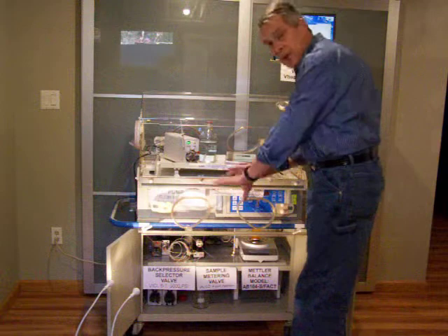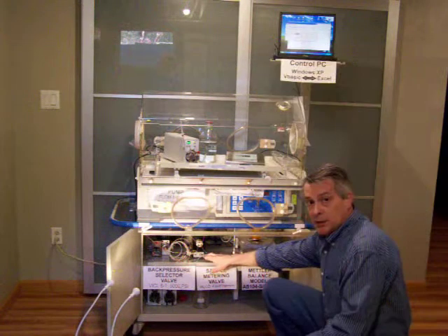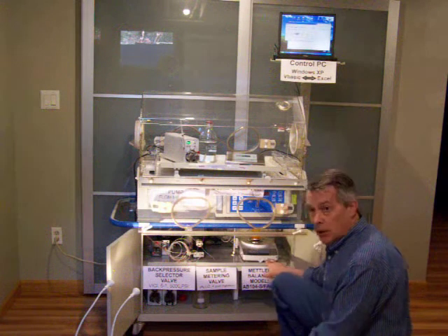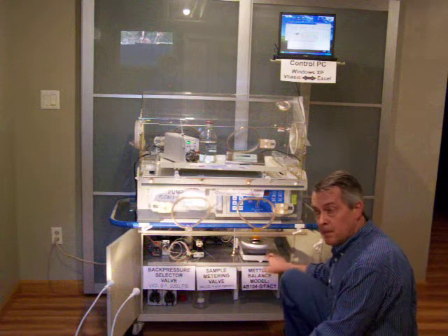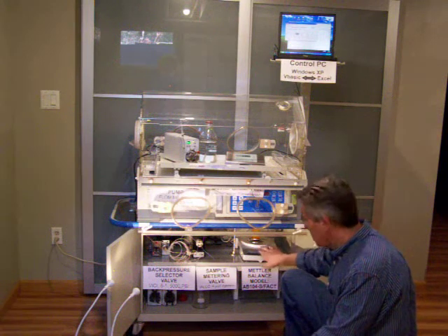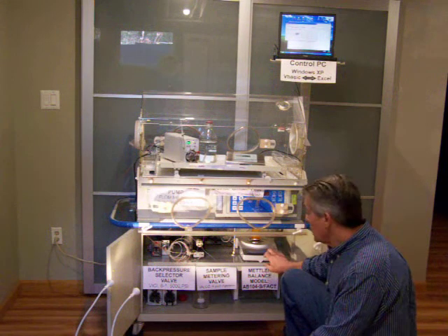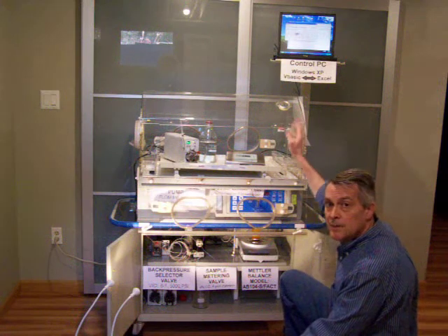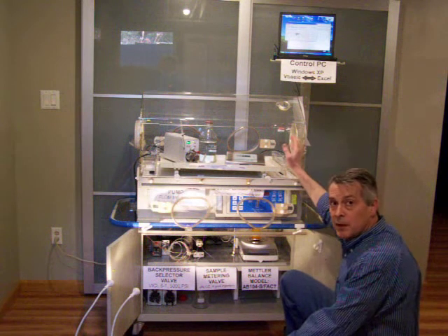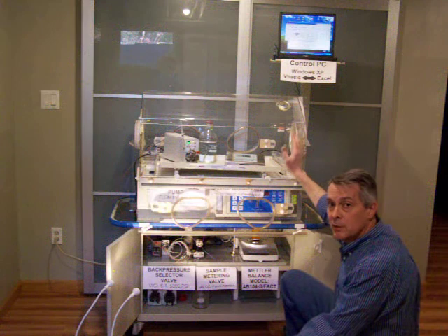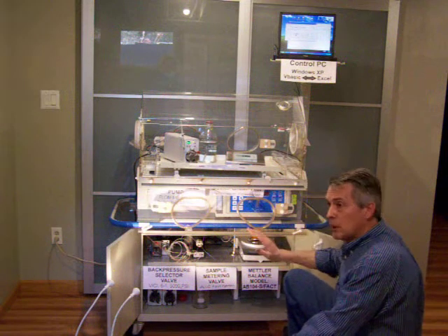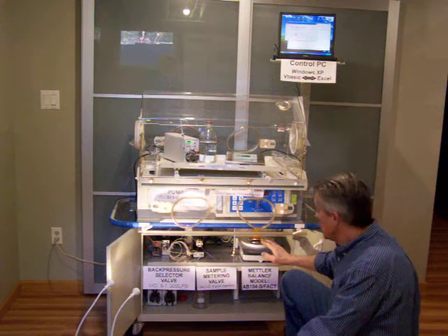After the flow rate is stabilized, it then gates the injector valve to gate fluid into the collector cup here on the Mettler balance. So the PC takes a reading. The time scale is controlled by the PC, which is more than adequate for this application, even running under XP.